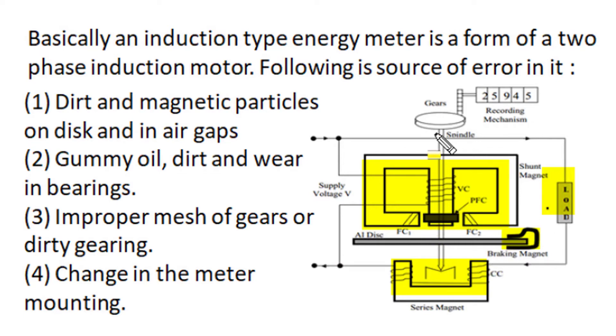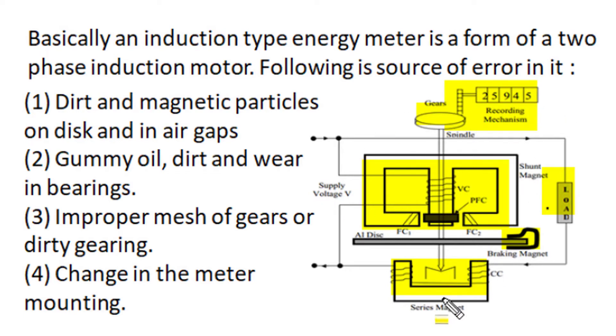The rotating disk experiences braking when it rotates across the brake magnet, and this braking torque is proportional to the angular velocity of rotation. In equilibrium, when driving torque and braking torque become equal and opposite, the rotation speed of the disk becomes proportional to power flowing through the meter. When we measure the number of rotations using a registering and counter mechanism, that measurement becomes proportional to the amount of energy flowing through the meter, giving direct energy results in the decimal counter.